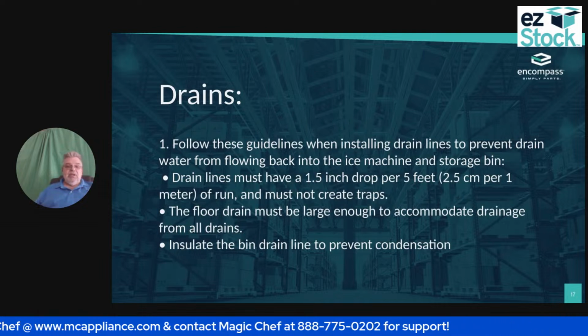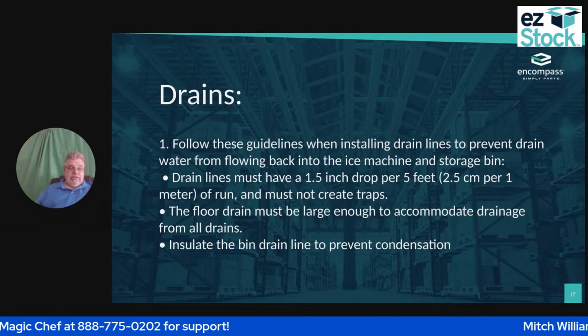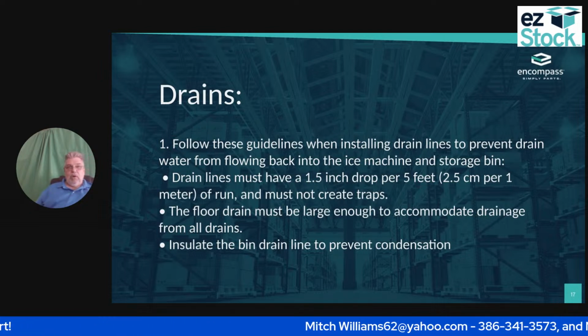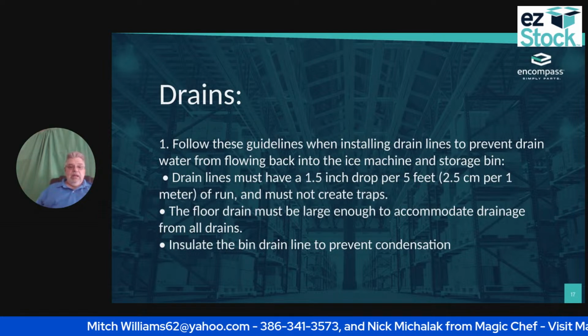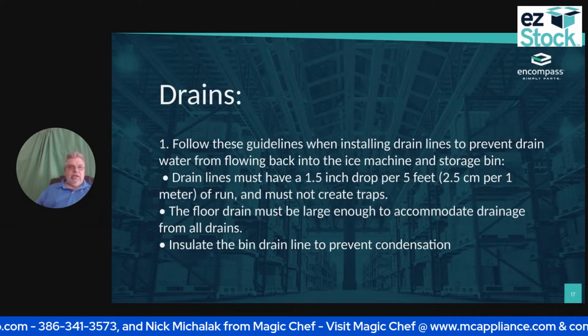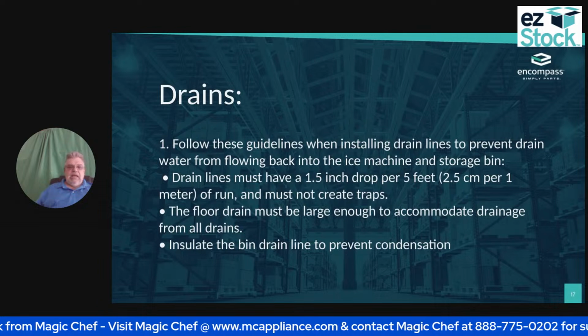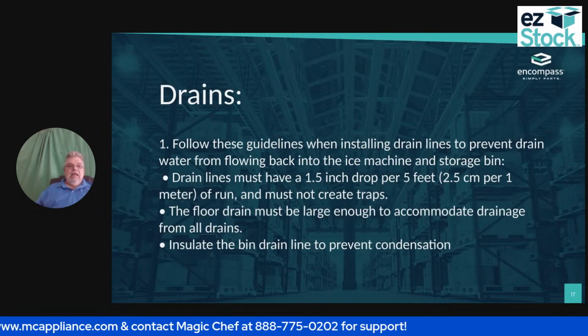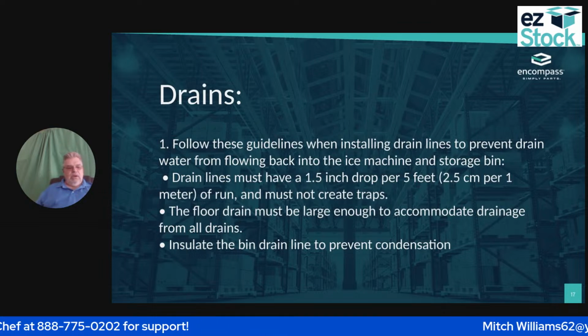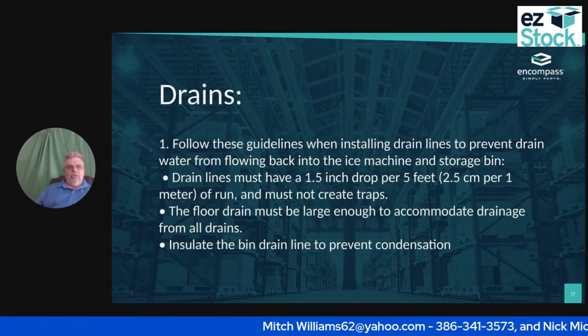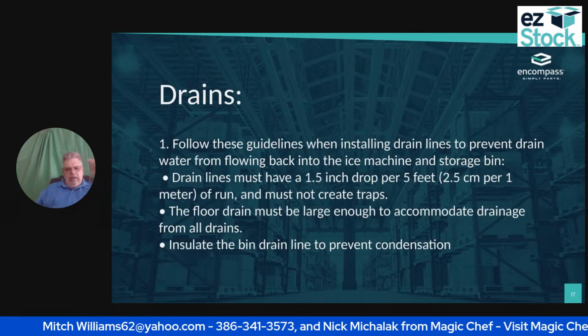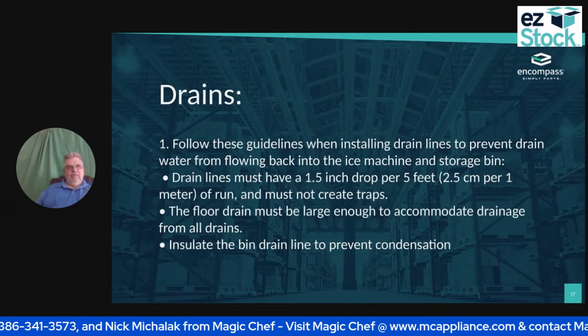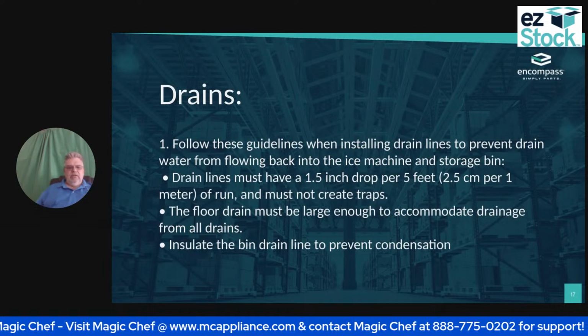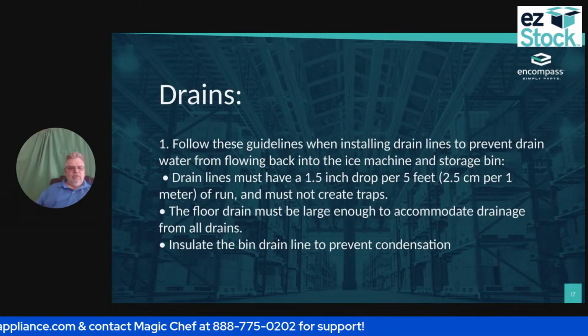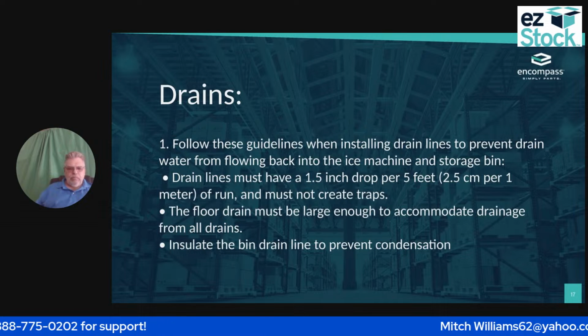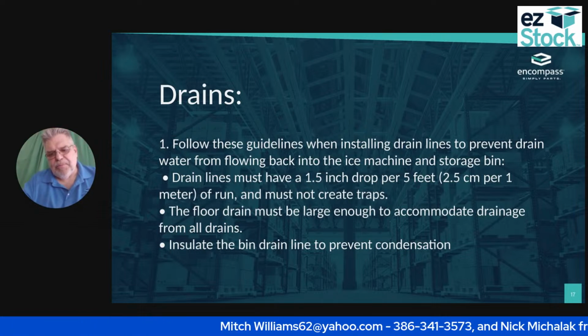So a floor drain has got to be large enough to accommodate drainage from all the drains. I worked for a very short while for the school system in Florida, and I had to go back and fix 2 or 3 of the drains because, number one, they didn't have the right drop. So I had to redo that. And then whenever I got done and it went through a cycle and it dumped the water out of the ice machine, I had to have somebody come in and change the filter in the drain because it was getting clogged. It wasn't large enough for the water to drain out of the system. So it backed up into the kitchen. Okay. So I'm going to insulate the drain line if I need to, to prevent any condensation.